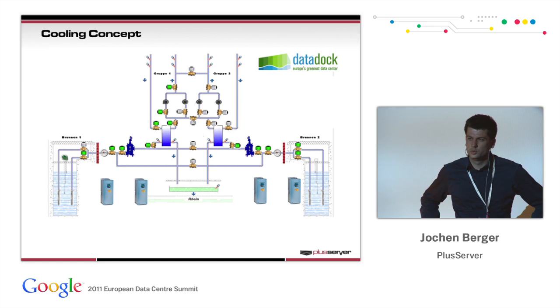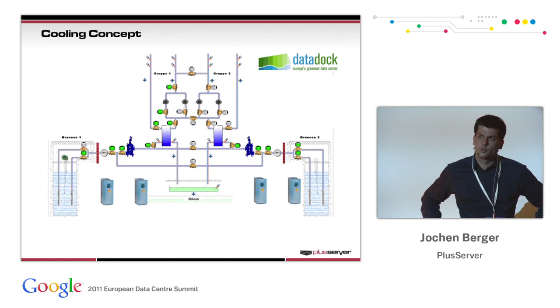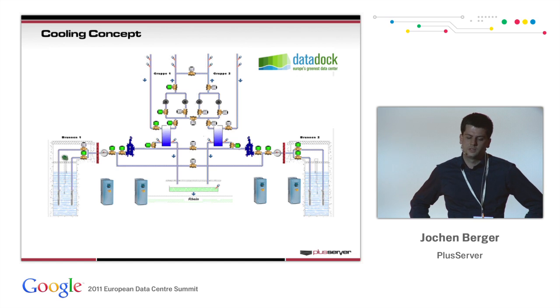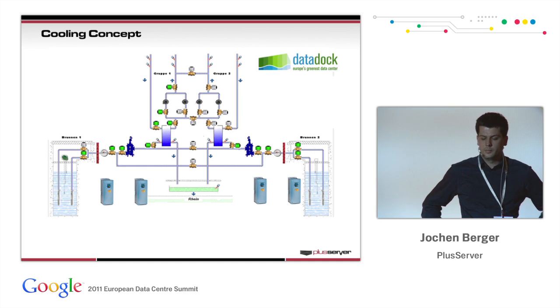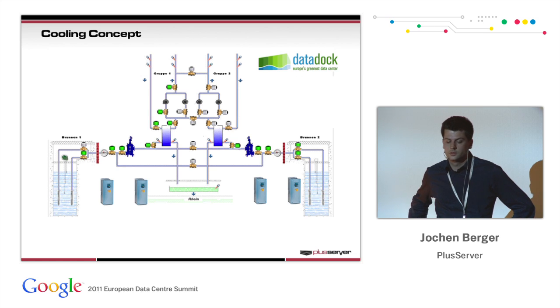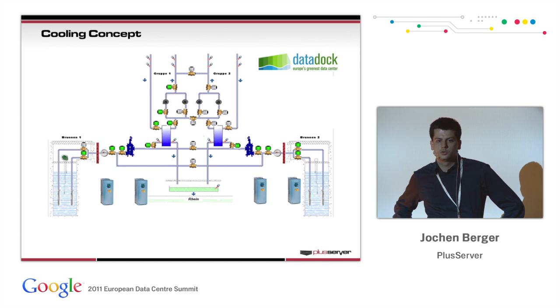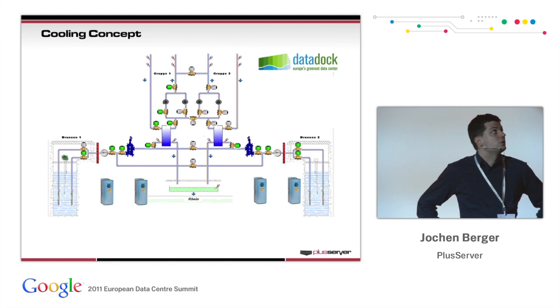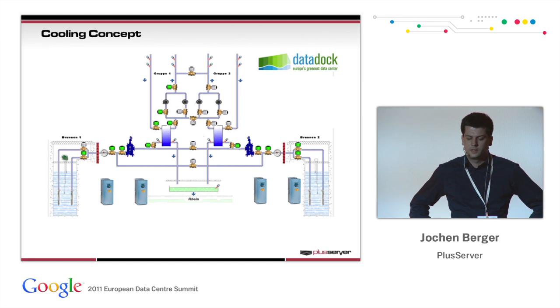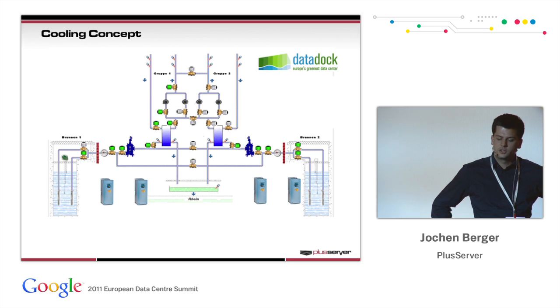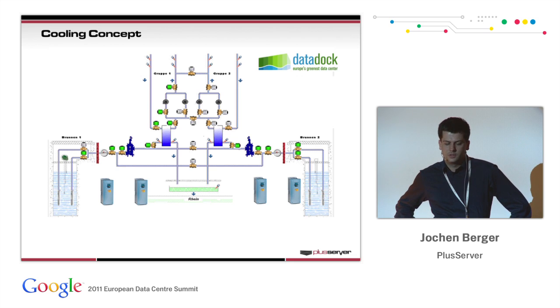So in general we are using 2 wells for full redundancy. Each of our wells is capable of giving us up to 680,000 liters per hour. We are running 2 pumps in each of the wells, once for redundancy, but also in order to get this volume of water out of our wells. Then we are filtering the water. If you have such big wells, you need to have some filters in order to prevent sand from getting into your heat exchangers. And these filters are just checking the water before it goes to the heat exchangers.